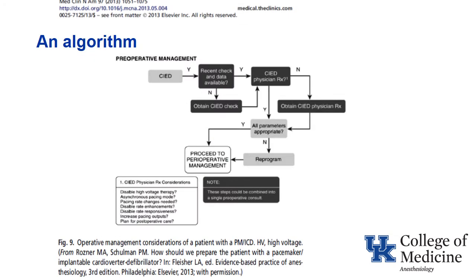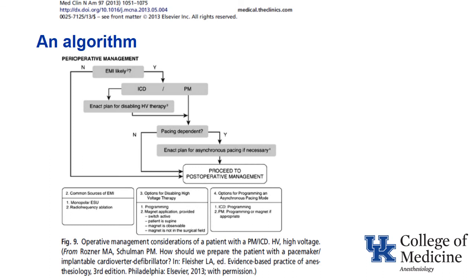Now here's an algorithm, and on this algorithm you see reference to a CIED physician in the preoperative management, and this refers back to the recommendation that there be an institutional solution for these devices. Now, following this algorithm, if EMI is unlikely, then you proceed directly to postoperative management.